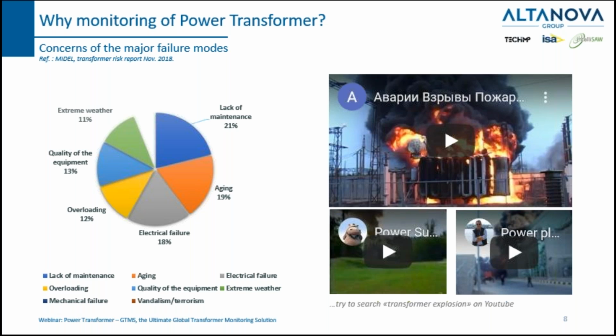On the left, I would also like to share with you some interesting figures. These figures are from a report from November 2018, and you can see a lot of percentages. These are the major failure modes. We can see here almost 20% for lack of maintenance, another 19-20% for the aging of the transformer, another 18% for electrical failure, and then overloading, the quality of the equipment, weather conditions, mechanical failures, and other aspects.